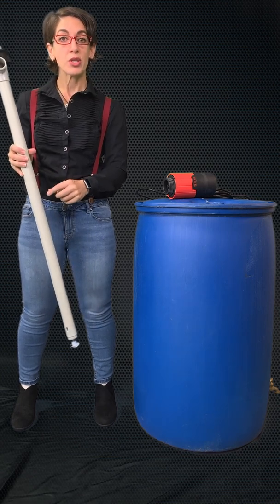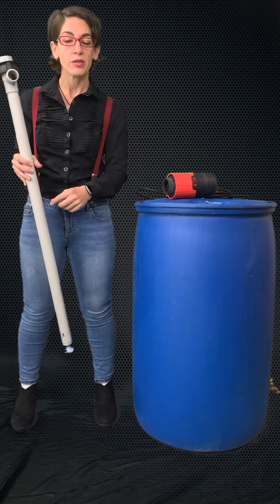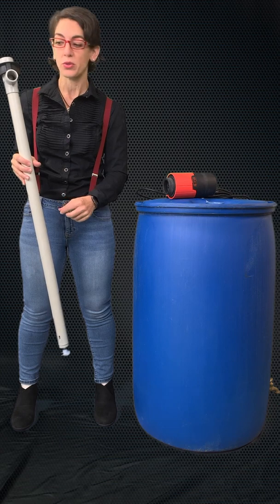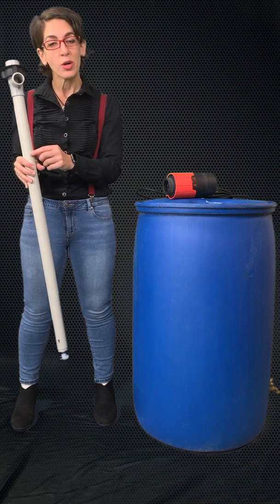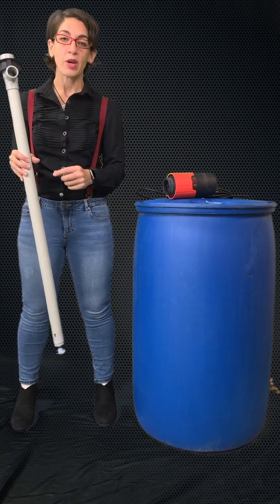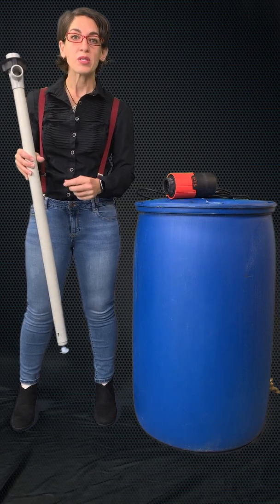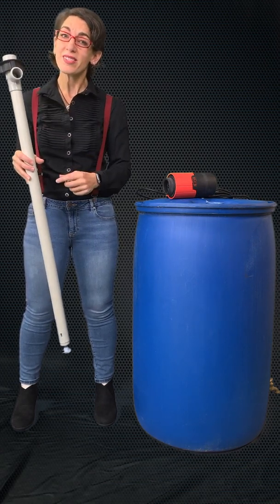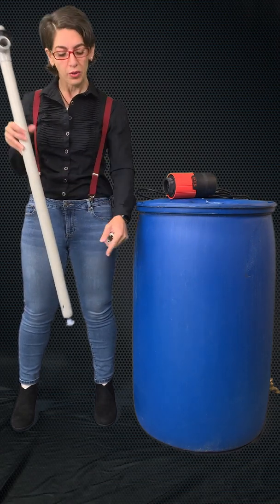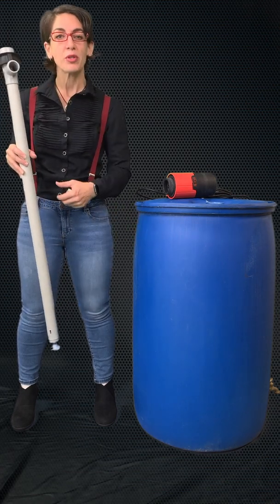They use a different material shaft—they use a Hastelloy C shaft instead of standard stainless steel for chemical compatibility issues. The shaft in these drum pumps is thicker than most of the manufacturers out there, giving it more stability. The shaft itself is reversible, so if one of the threads goes on the bottom, you can flip it internally, so you get two times the life of it.